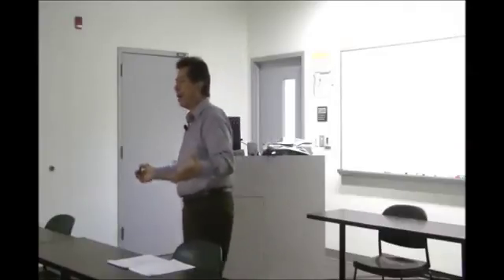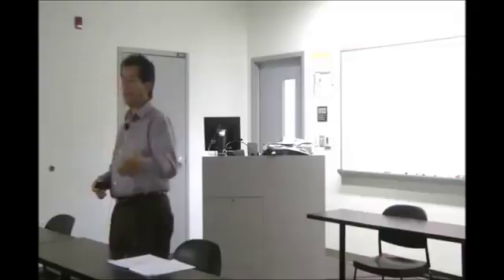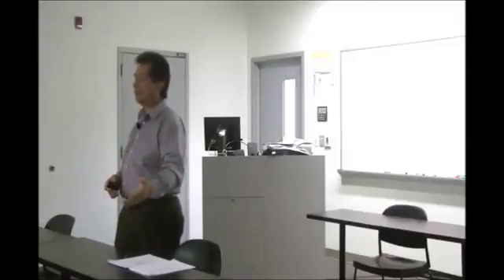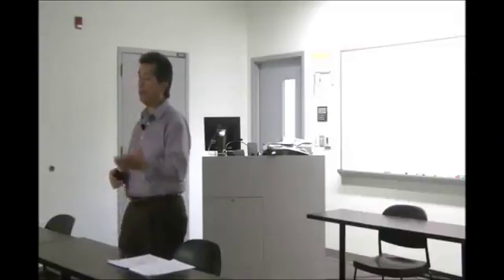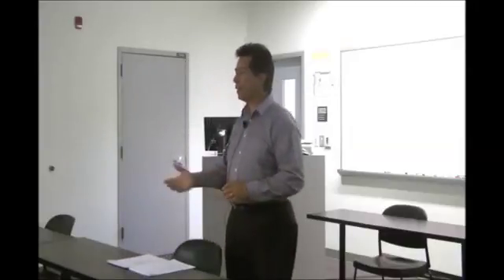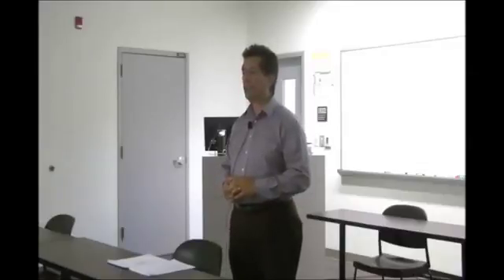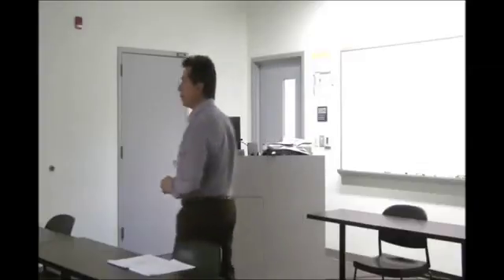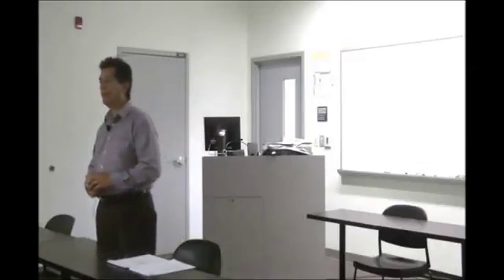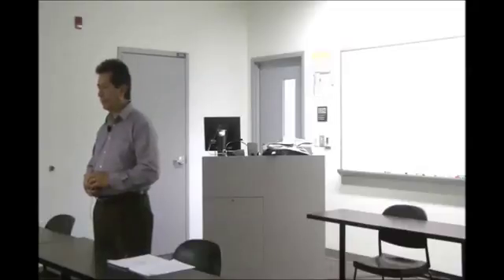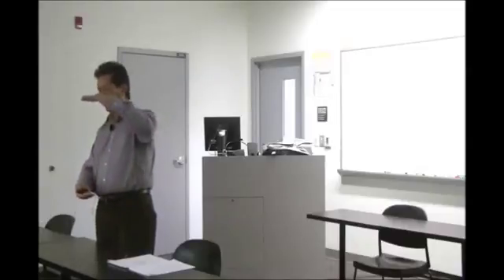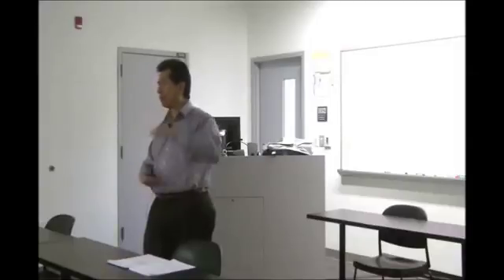Now we'd get a call: I'm too hot, what are you guys doing? We've got to drop the temperature, so we'd drop it to 70, and it would overshoot and drop to 64 degrees. What do you think our customers were thinking of facilities? What are you guys doing, right? So they came back and took out my manual valves. I couldn't believe the size of valves they put in, little electronic ones about that tall. They went from 6 inch down to 4 or 4.5, and from 8 inch down to 5 or 5.5.